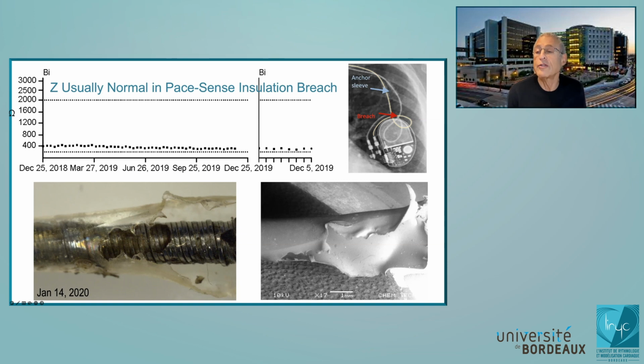We call these little things shims, and those are what mechanical engineers call separators. We separated the can from the lead, from the insulation breach, by shims, and started with a quarter millimeter, half a millimeter, and that sort of thing. And then we measured impedance. And it turns out that basically to measure an abnormal pacing impedance, you have to have direct metal to metal contact between the can and the lead. And even if you just put the lead on top of the can, it doesn't always become a low impedance, because the actual metal is separated by the thickness of the insulation on both sides of the breach. Am I making sense? Maybe I'm not making sense.